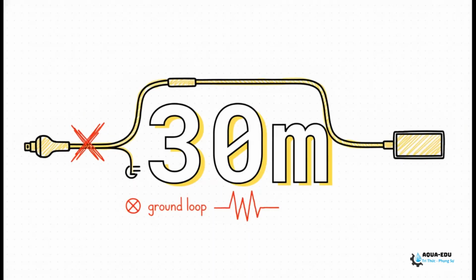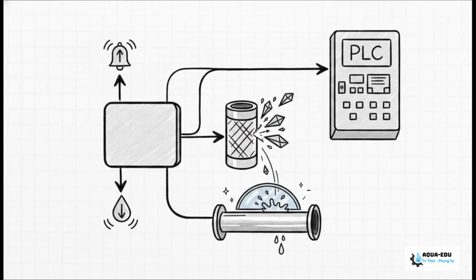Okay, write this number down, 30 meters. The pH electrode has an extremely high impedance. Because of that, your shielded coaxial cable length must never, ever exceed 30 meters, or you're going to get severe signal loss. Also, you must only ground the shield drain wire at the transmitter end. Never ground both ends. If you do, you're going to create a ground loop that will severely distort all your readings. As you wire up the terminal block, double-check your specific model.